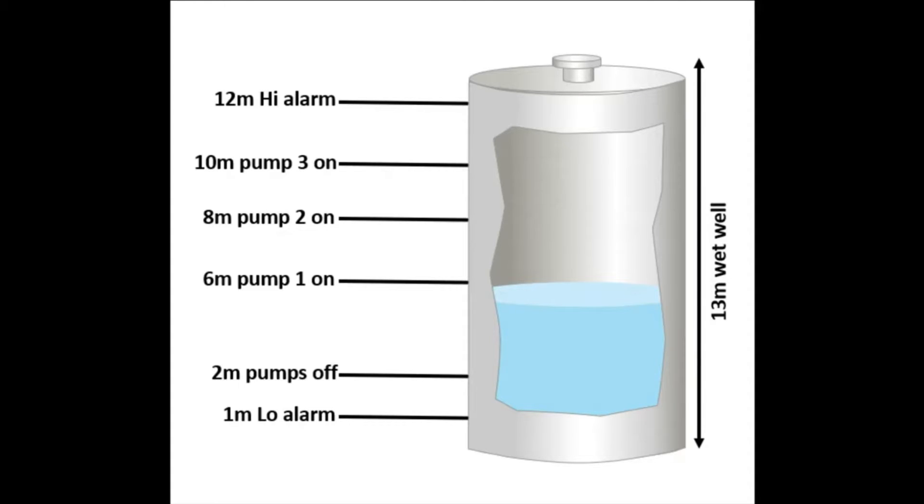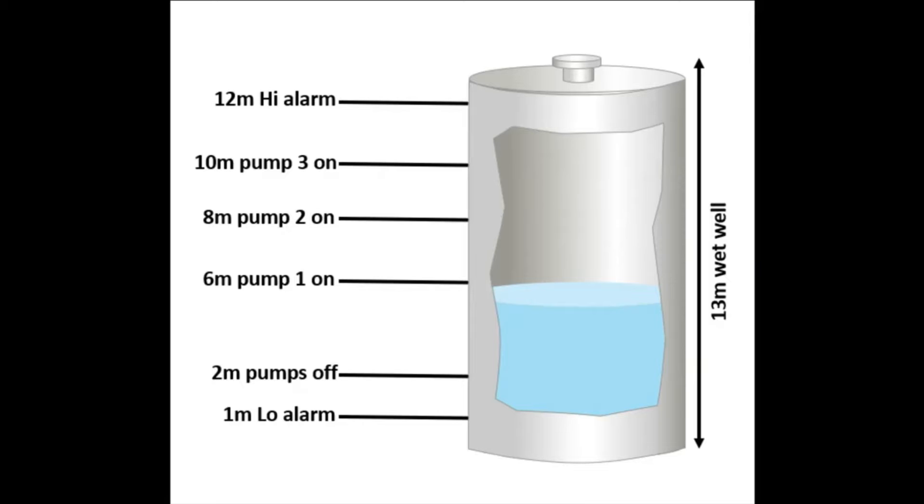They have three pumps which they would like to alternate in order to remove the liquid from the wet well, one that comes on at 6 meters, another at 8 and a third at 10 meters of level. All three pumps will turn off at 2 meters of level.